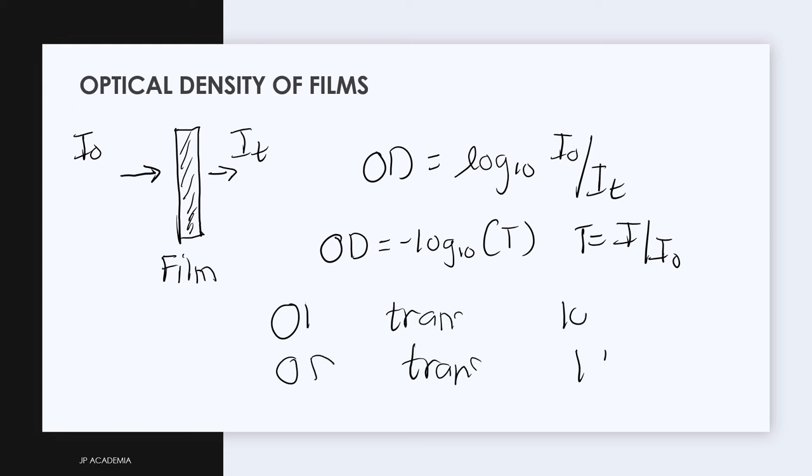The transmittance T is just the fraction of the visible light passing through the film from the light source. Now OD, if your OD is equal to 1, it transmits 10%, and if your OD is equal to 2, it transmits 1% of the initial intensity.